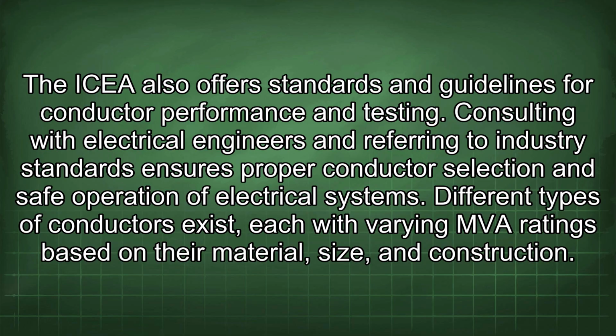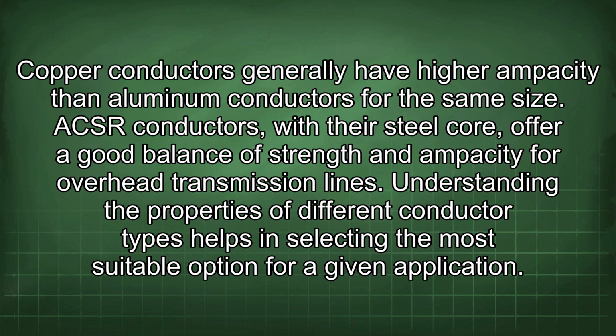Different types of conductors exist, each with varying MVA ratings based on their material, size, and construction. Copper conductors generally have higher ampacity than aluminum conductors for the same size. ACSR conductors, with their steel core, offer a good balance of strength and ampacity for overhead transmission lines. Understanding the properties of different conductor types helps in selecting the most suitable option for a given application.